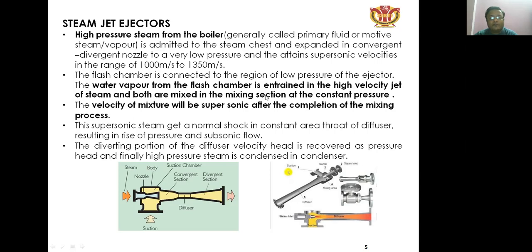The water vapor from the flash chamber is entrained in the high velocity jet of steam and both are mixed in the mixing section at a constant pressure. The velocity of the mixture will be supersonic after the completion of the mixing process. This supersonic steam gets a normal shock in the constant area throat of the diffuser, resulting in rise of pressure and subsonic flow.